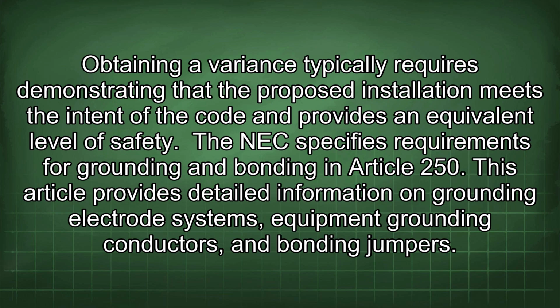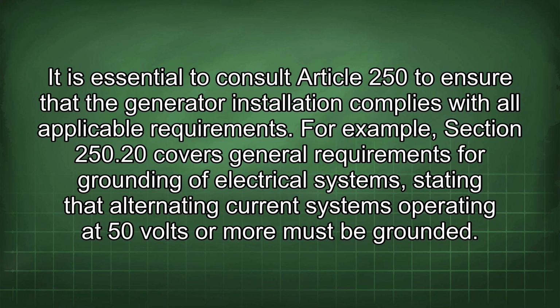The NEC specifies requirements for grounding and bonding in Article 250. This article provides detailed information on grounding electrode systems, equipment grounding conductors, and bonding jumpers. It is essential to consult Article 250 to ensure that the generator installation complies with all applicable requirements. For example, Section 250.20 covers general requirements for grounding of electrical systems, stating that alternating current systems operating at 50 volts or more must be grounded.